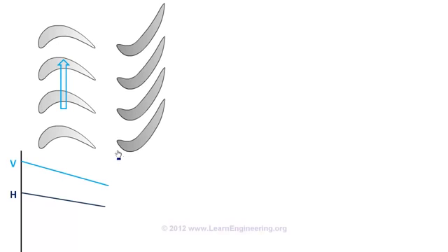Stators are also a set of blades, but these blades are stationary, and they won't take part in the energy transfer. What it does is simply transform energy from one form to another. Or more precisely, it will transform the enthalpy energy into kinetic energy. You can see the cross-section area of the nozzle decreases with flow, so due to its special shape the velocity increases. But at the same time enthalpy decreases. If you sum the change in enthalpy and kinetic energy, there won't be any change.